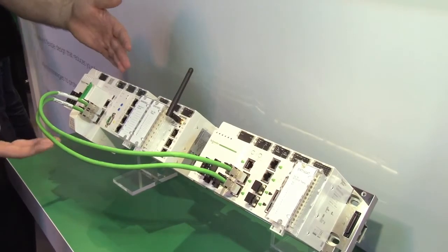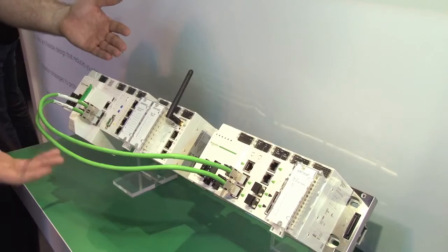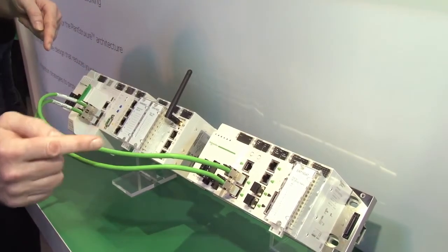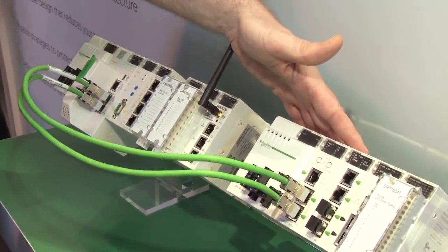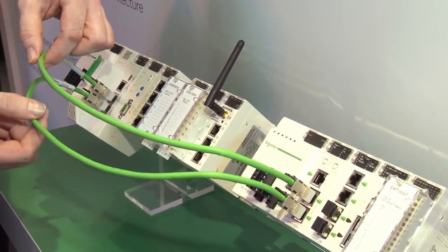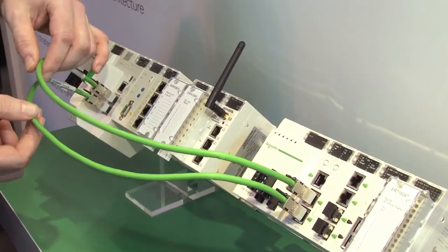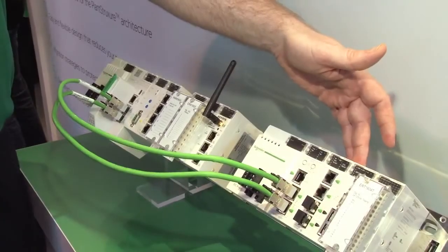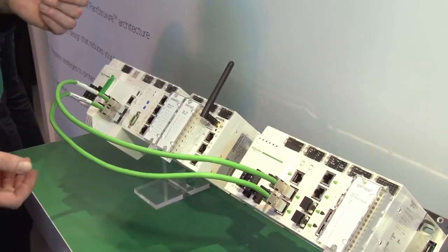What else can we see on the M580? Well, let's have a look at here. We've already talked about the inbuilt Ethernet backplane, but that extends through the green cables on the front here. We can see that we're looping across. We've actually got a redundant connection here. So two cables from the CPU into our first block of remote I/O, and then back again to the processor. So if one cable is severed, we've still got an alternative connection back. Copper cable is usually good for about 100 meters. If you need to extend, then we've got in-rack fiber optic modules, which we can extend the distance between racks up to several kilometers if we need to.